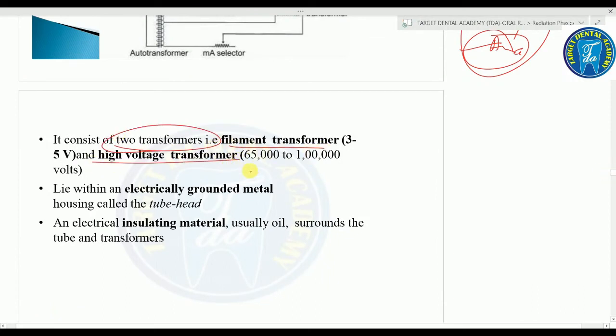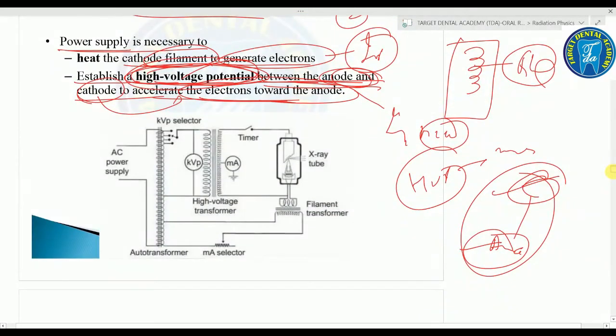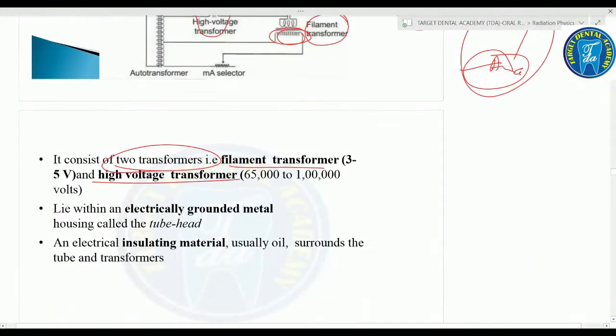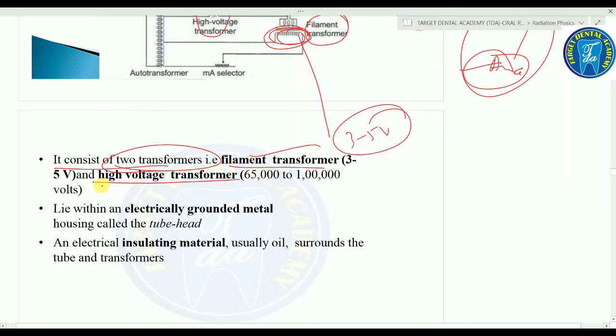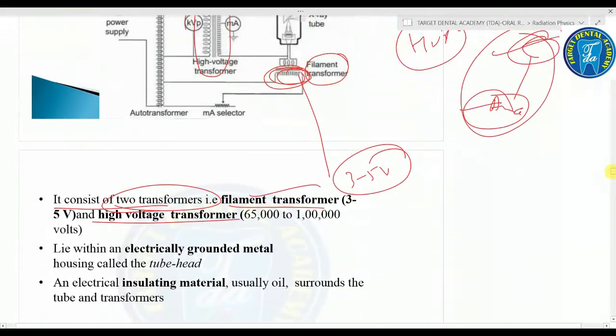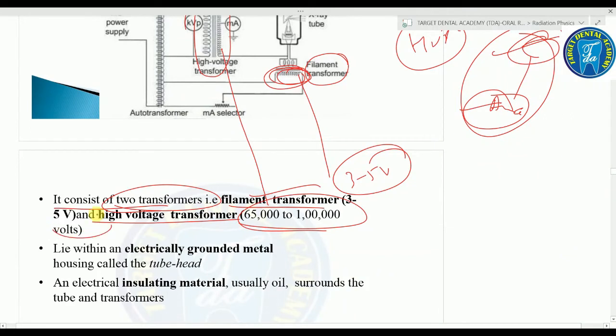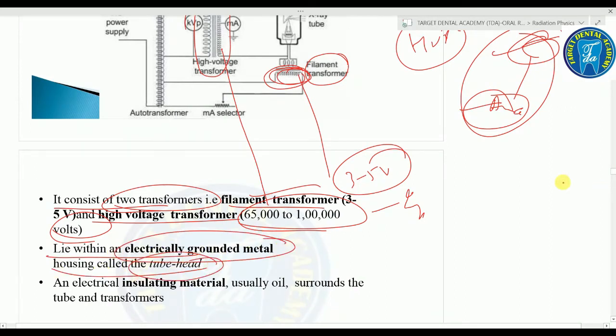The filament transformer is the small one — 3 to 5 volts. The high voltage transformer provides 65,000 to 100,000 volts. These transformers lie within the electrically grounded metal housing called the tube head, surrounded by electrically insulating oil.